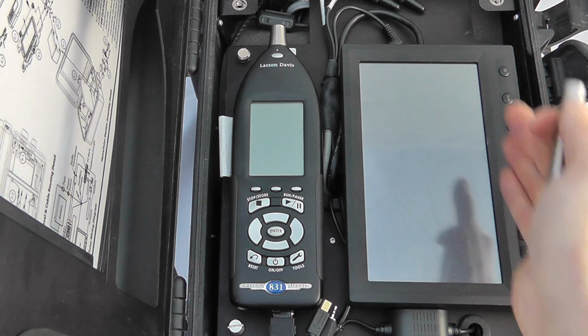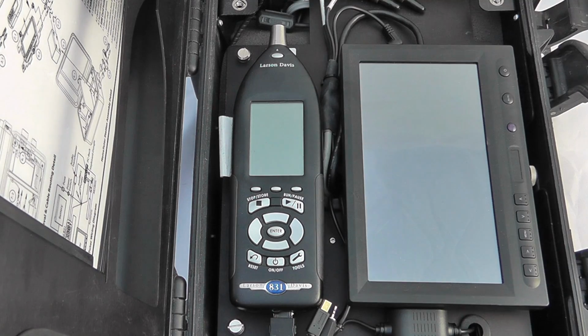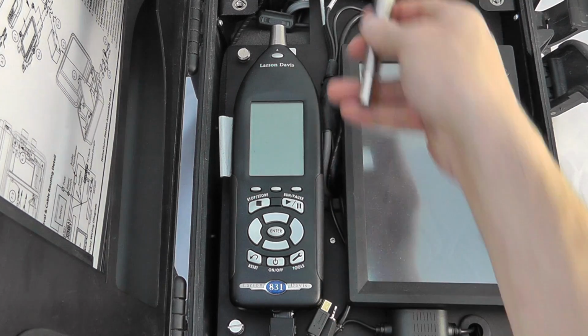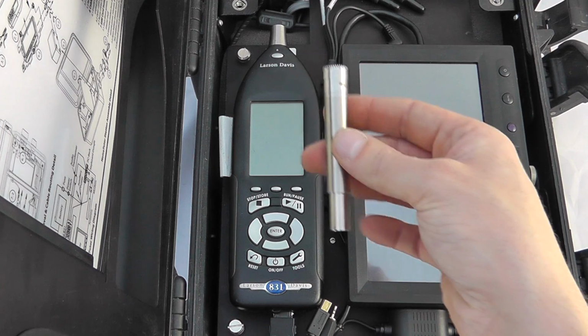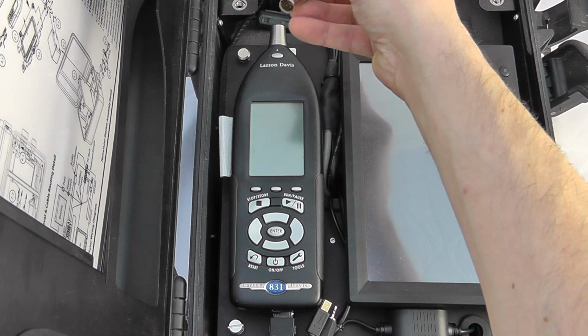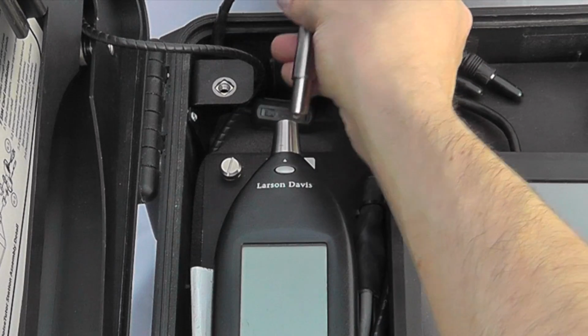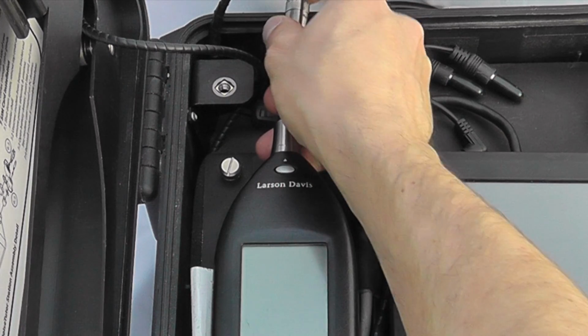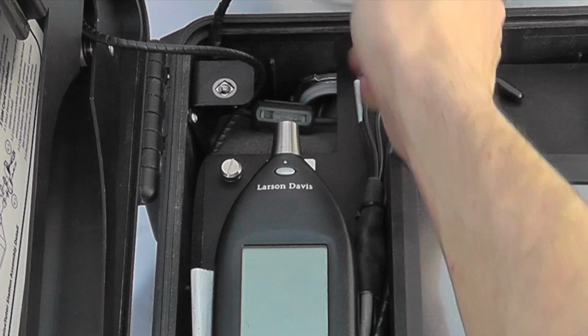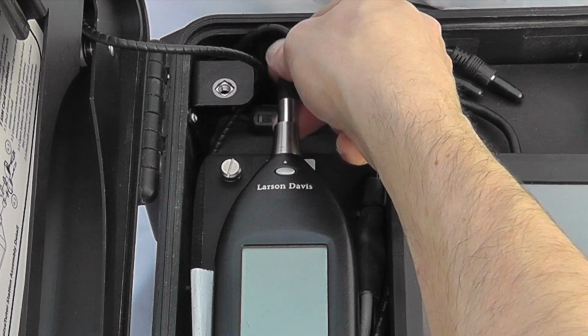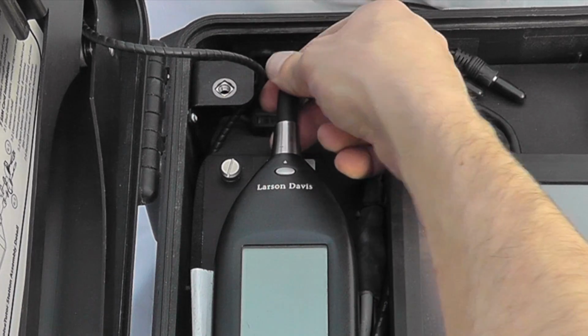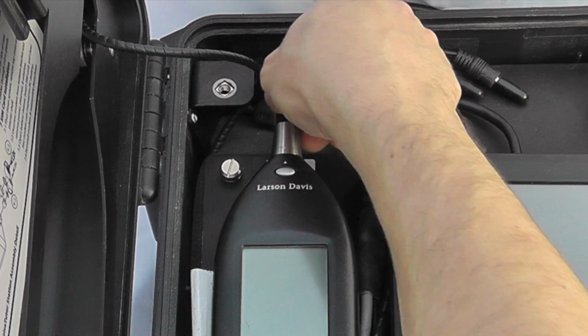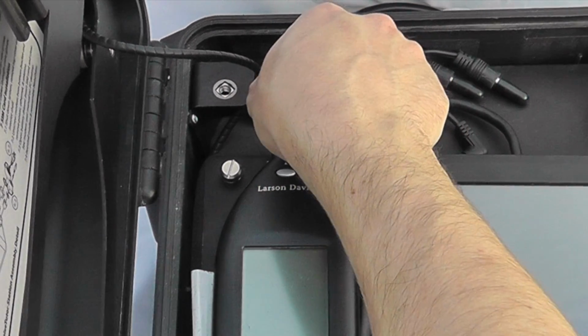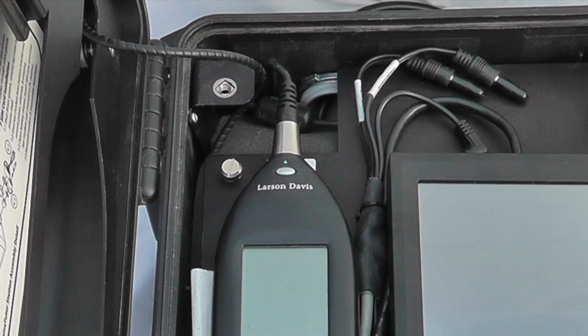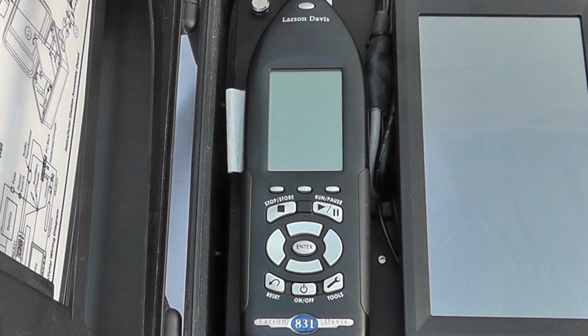This happens to be installed as part of a noise tutor system, but operationally it functions exactly the same way as a handheld instrument. I have the mic and preamp pre-assembled. This inserts into the top of the instrument and will only go in one fashion. We can insert it in this way, or in this particular instance we're going to use the mic extension cable, which is integrated into the noise tutor system, and I will install the mic into the external microphone extension cable.